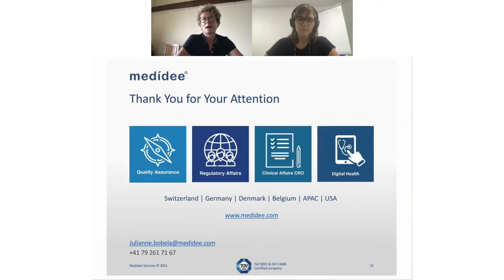Also, we have to link it to the risk assessment, and we have to keep in mind that risk assessment is closely linked to the PMPF activity. So if you have data from your post-market surveillance that shows there are some risks related to the use of the device because of some misuse or additional risks, those should be in the risk assessment and should be reflected in your performance evaluation report as well.